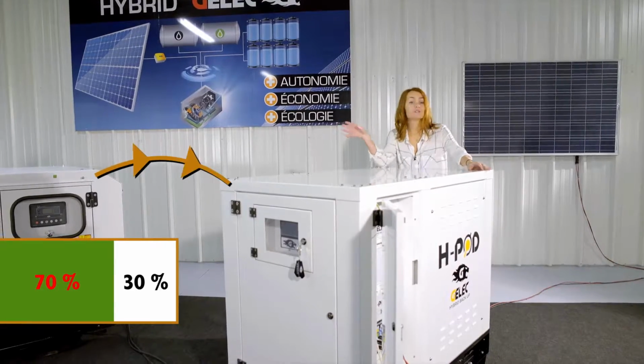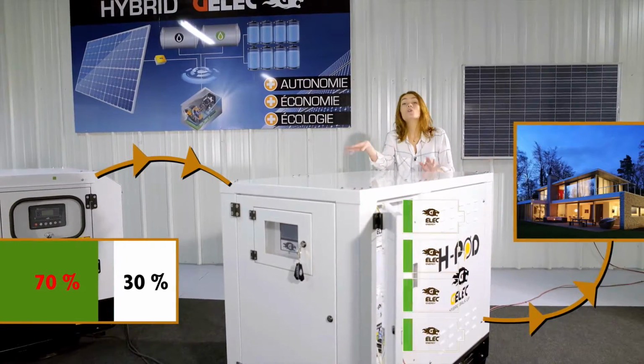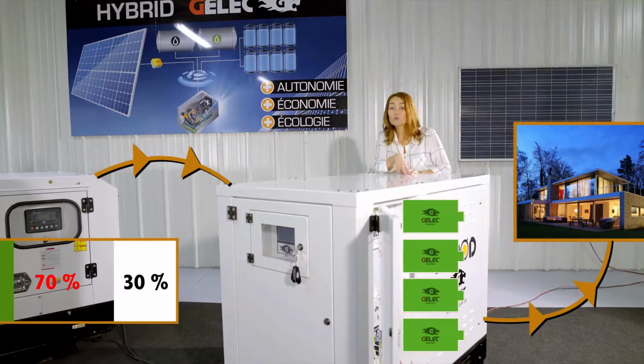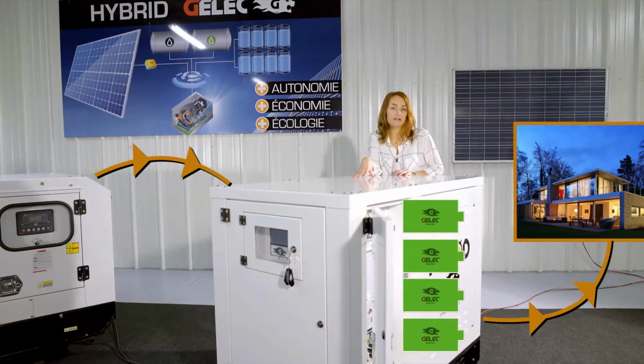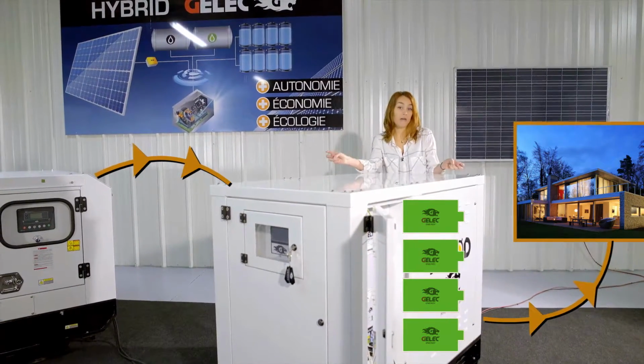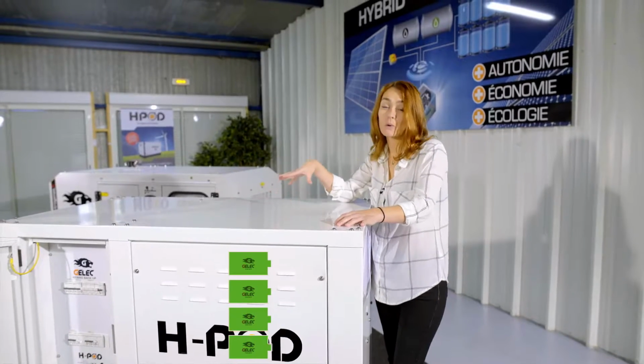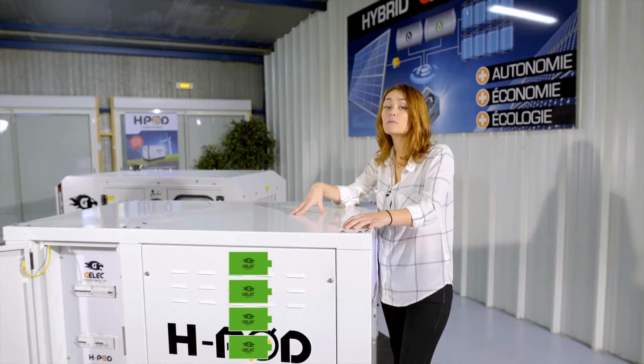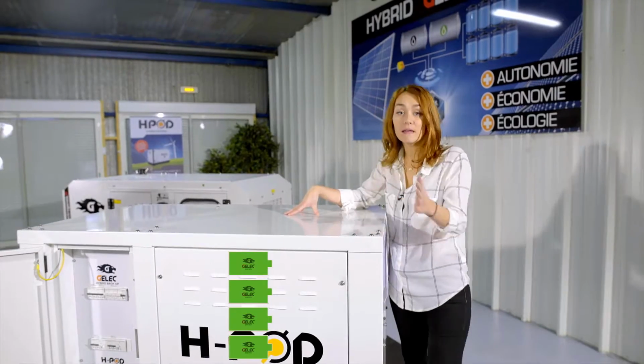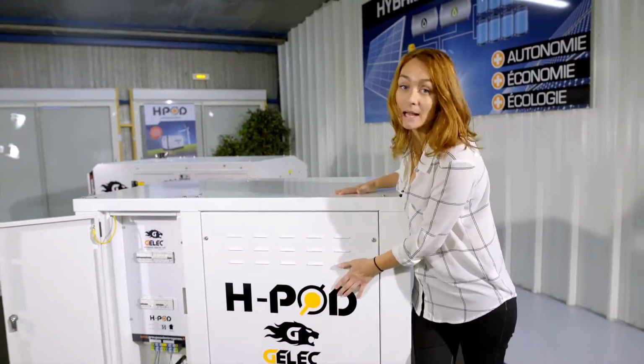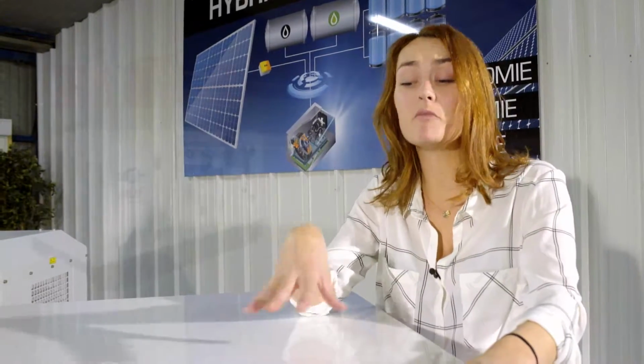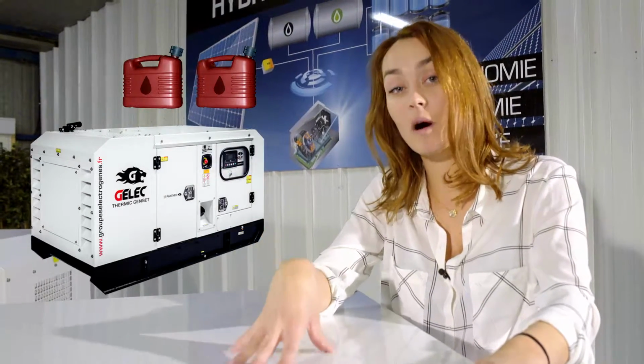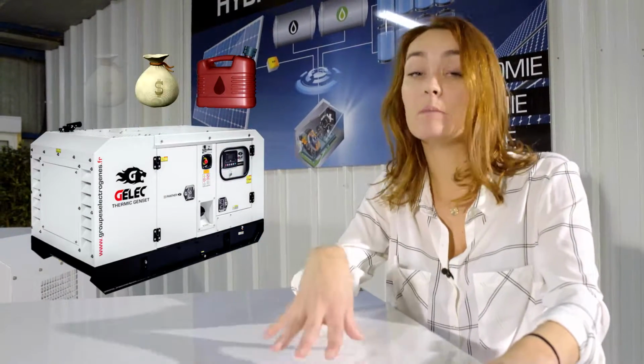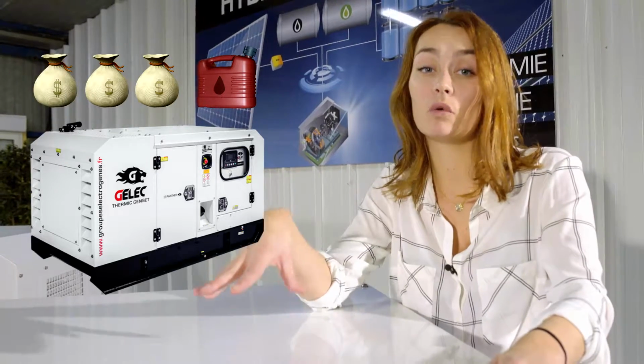If you place the HPOD between the generator and your application, it will store the excess of energy, which would normally be the 70% lost. As soon as the HPOD batteries are full, it will automatically stop your genset and you will be supplied by the batteries. This technology will allow you to divide your fuel consumption by 3 and triple the lifespan of your generator.